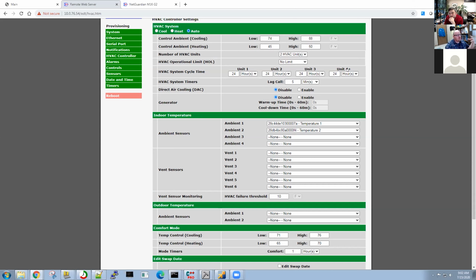But some of this you might want to come in and tweak. This is basically the defaults we'd get on a fresh configuration. We can see here, number of HVAC units is set to 2. HVAC operational limit—I know one client had 6 HVACs but only wanted at most 3 running at any one time. So the HVAC operational limit was a feature to let us have up to 6 HVACs in a ring but prevent the scenario where all 6 run at the same time.